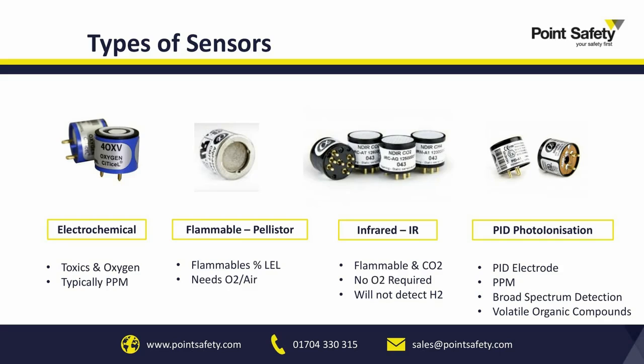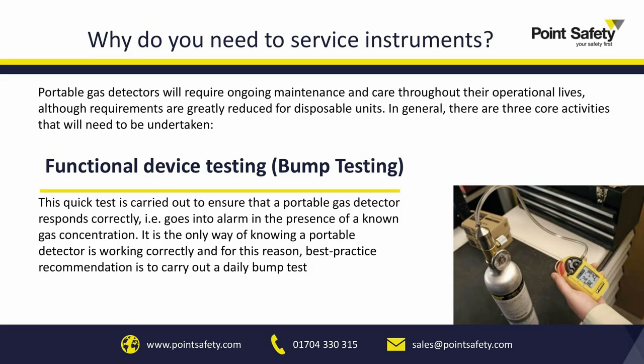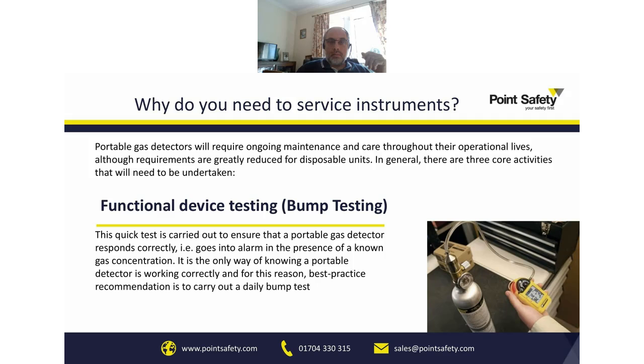So that gives us a brief overview of what types of sensors were within that range of meters we had before. So why do we need to service these instruments? Why is it important? Primarily, gas detectors require ongoing maintenance throughout their lives. Again, as mentioned before, this is reduced for disposable units, although they do still require bump testing, which I'll go on to in a moment.